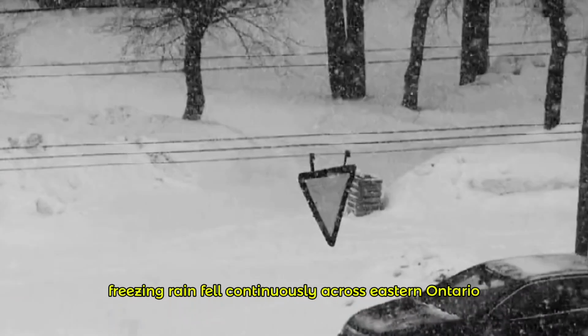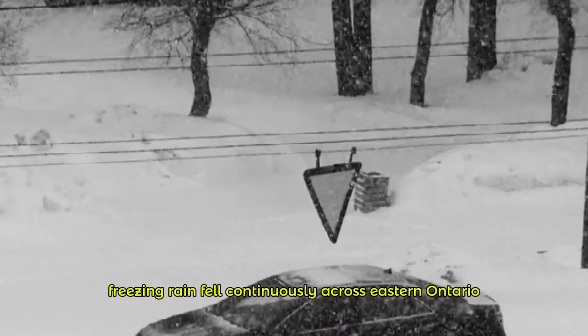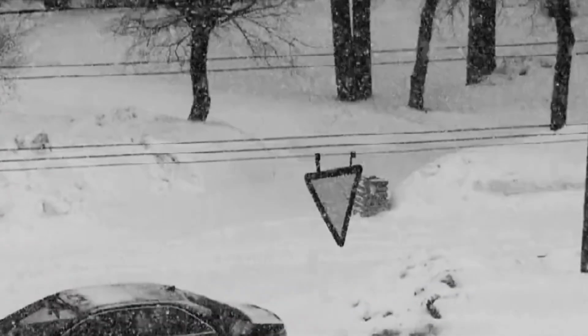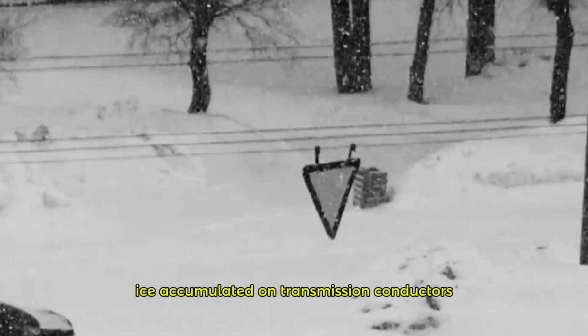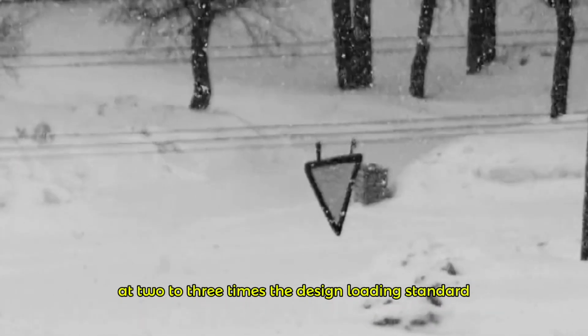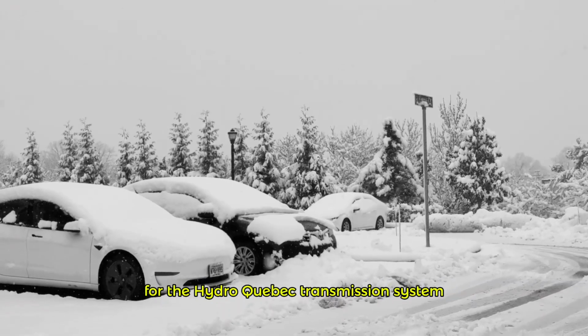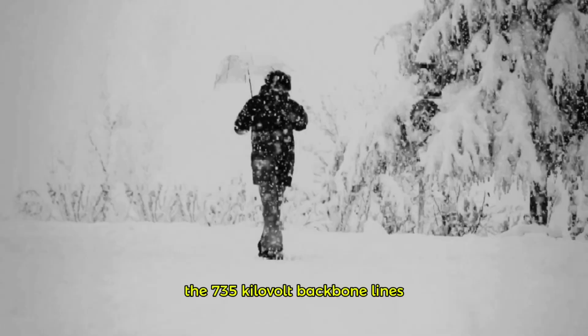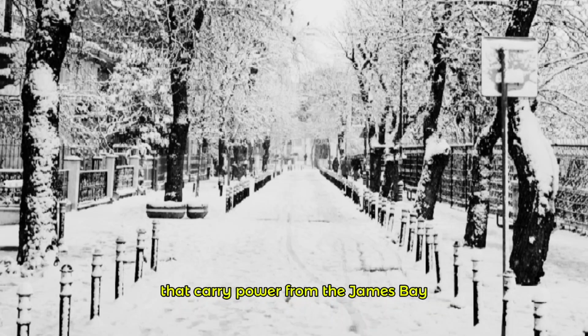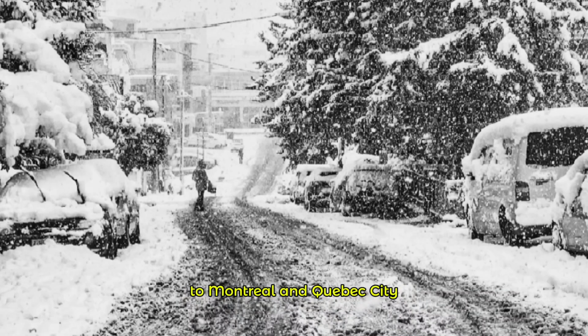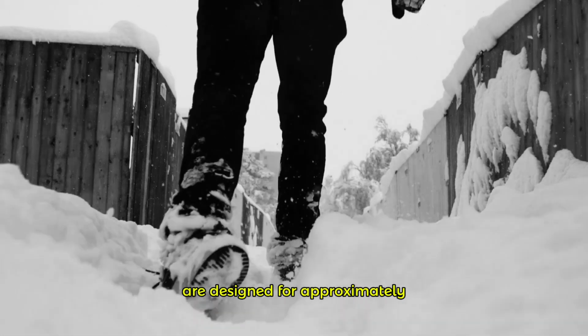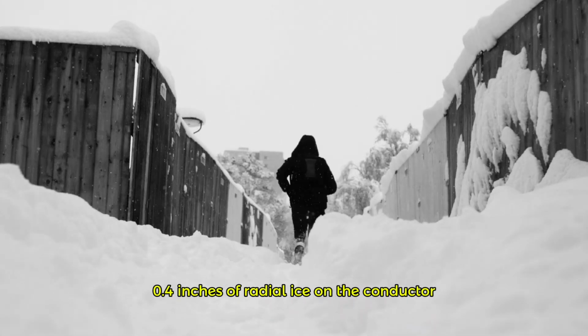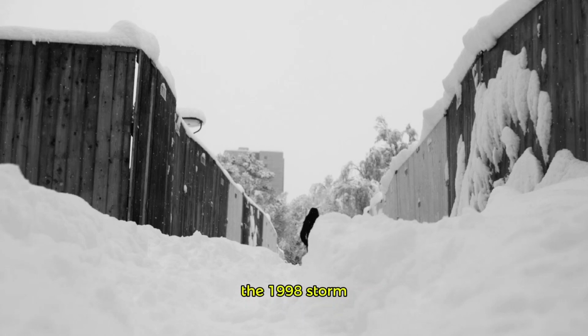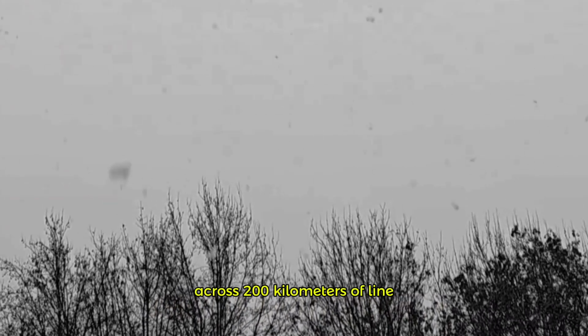Between January 4th and January 10th, 1998, freezing rain fell continuously across eastern Ontario, Quebec, and northern New England. Ice accumulated on transmission conductors at 2 to 3 times the design loading standard for the Hydro-Quebec transmission system. The 735 kilovolt backbone lines that carry power from the James Bay hydroelectric generating stations to Montreal and Quebec City are designed for approximately 0.4 inches of radial ice on the conductor. The 1998 storm deposited 2 to 3 inches of radial ice across 200 kilometers of line.